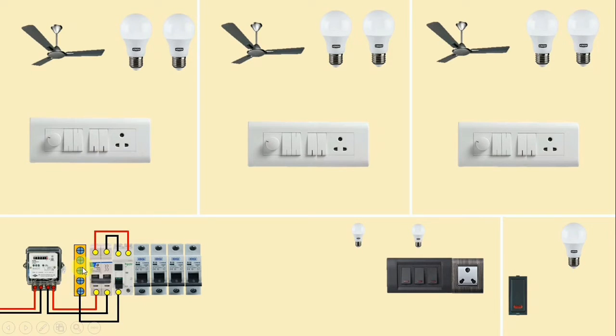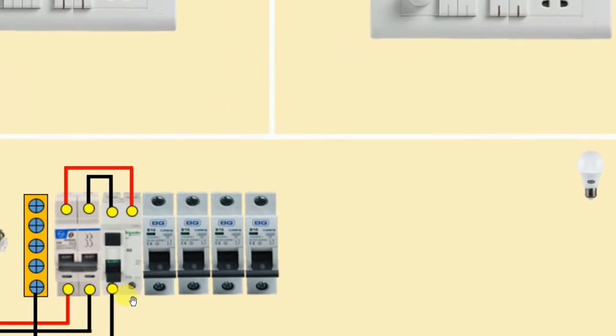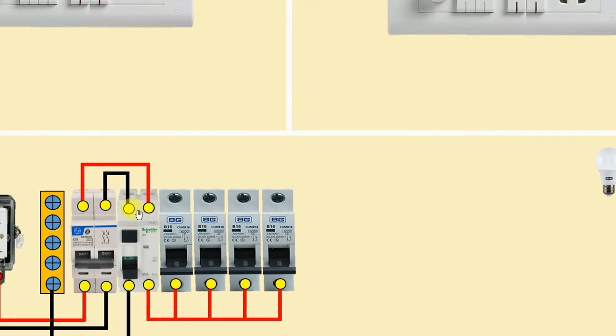So you connect your neutral to the neutral bar. This bar here is actually the neutral bar, where all the neutrals that are going to be distributed to the homes, to the rooms, are going to be connected. Then you connect and distribute the live wire too, because these small miniature breakers only take in the live cable, they do not take in the neutral cable. So all the neutral cables are going to be connected to the neutral bar, while the live cables are going to come directly into these breakers from the various rooms as they travel to those various places.